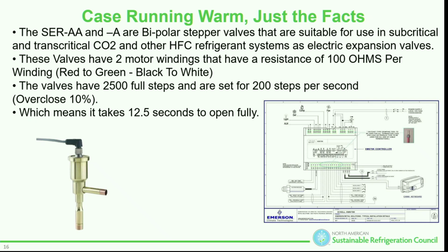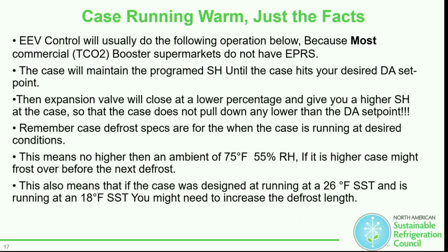And we all know in mechanical refrigeration, what is that an issue? That's usually a valve hunting because it's so oversized. Still refrigeration, still can happen in this aspect as well. The EEV control will typically do the following operation because most commercial transcritical CO2 booster supermarkets do not have EPRs. Not saying that they don't, but most of them do not. So because they're not able to control the suction pressure, there's a lot of times where that thing is going to pull down temp, shut off, and then come back up in temp, and then just keep operating.